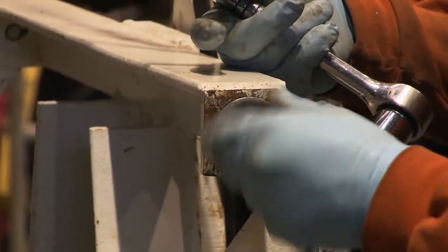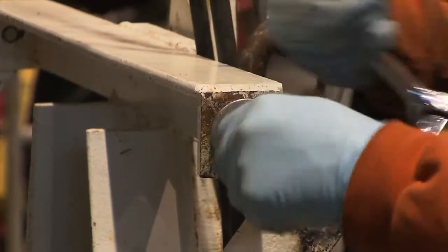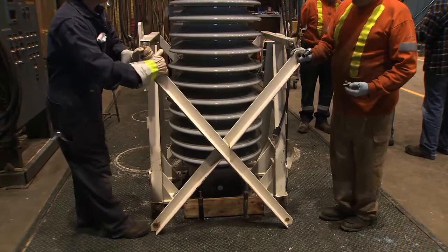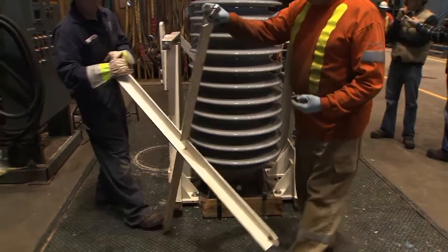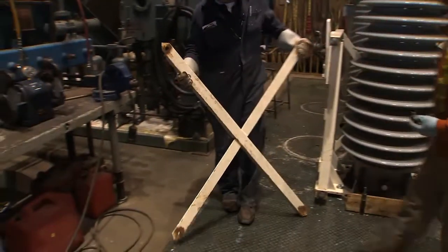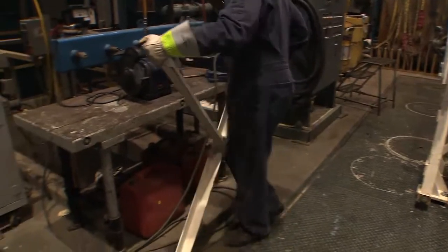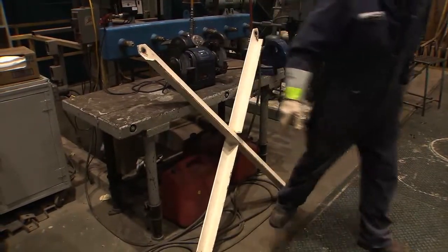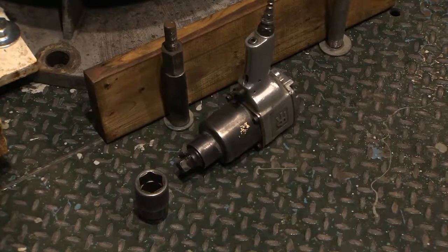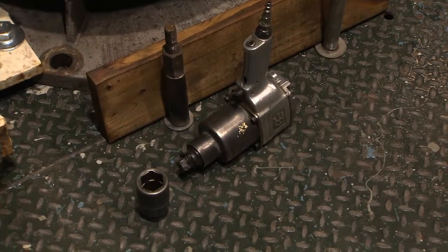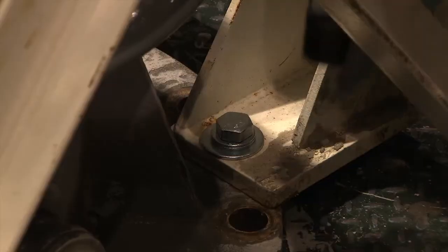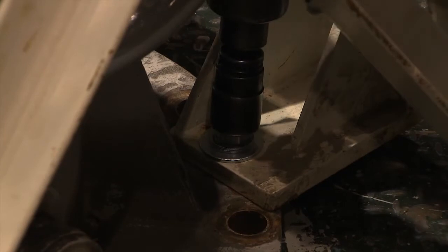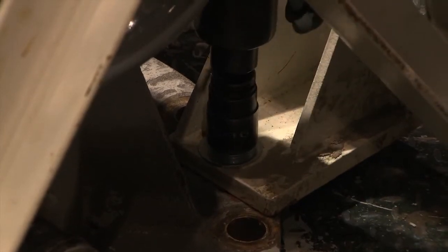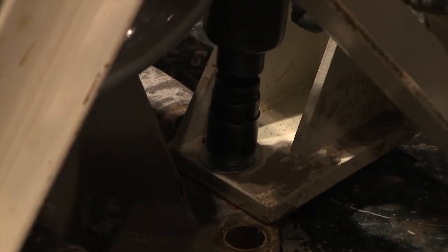This bushing is only put in this spot because of the holes in the floor to put the rods and the board in place so it can be uprighted in a stable manner. The cross-section is taken off from the jig and stored in a safe area away from the bushing. Use a pneumatic gun to take out the nuts and bolts that hold the lifting jig onto the flange.